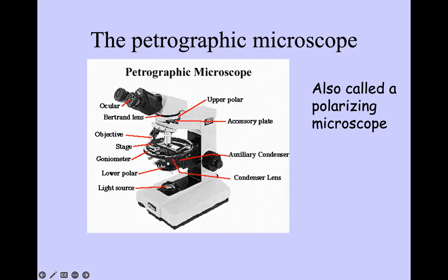So you will see an image of the sample through this eyepiece, since your light ray starting from here travels through this objective and then comes to this lens, right? So the magnified image will be further magnified by this ocular, by this eyepiece, because the eyepiece also has a typical magnification of 10 times, right? So whatever magnified image you are getting here will be magnified a further 10 times by this eyepiece.